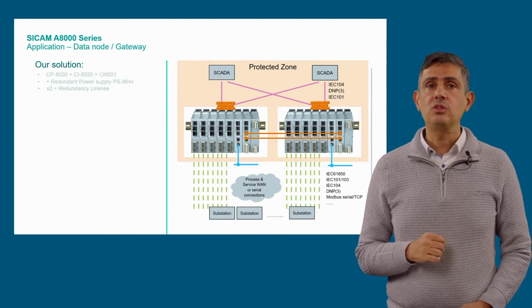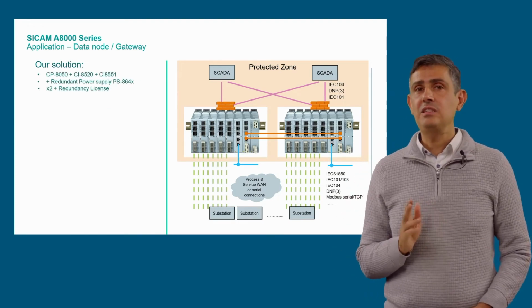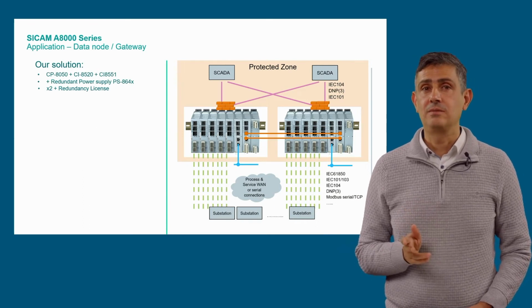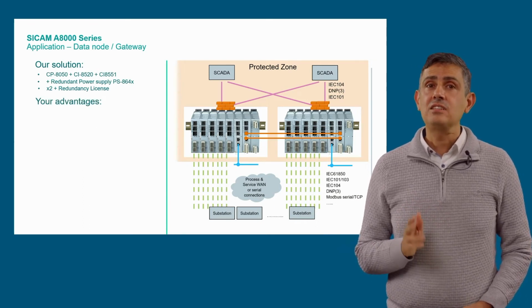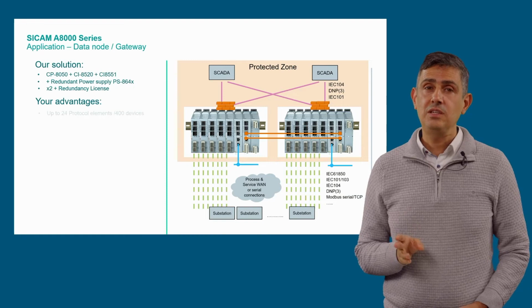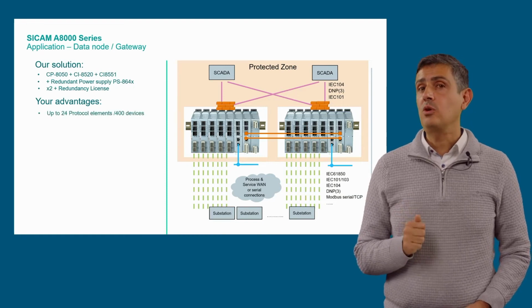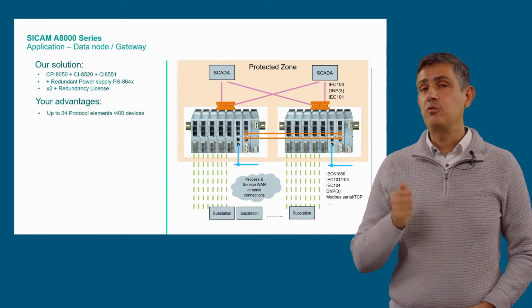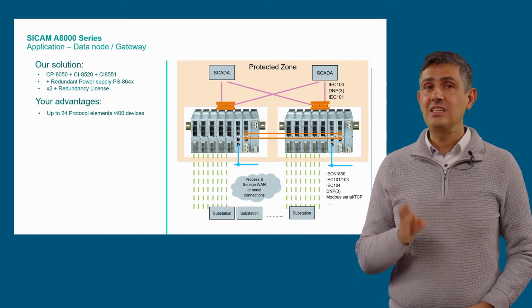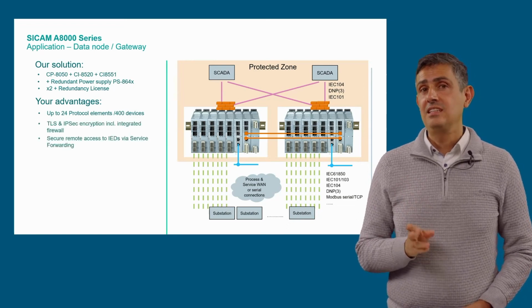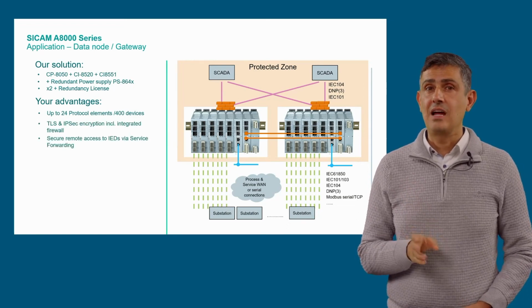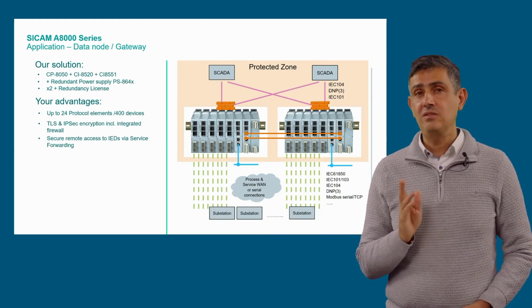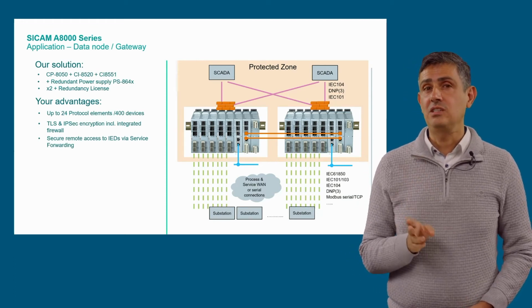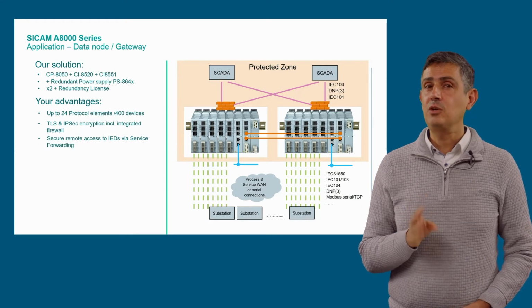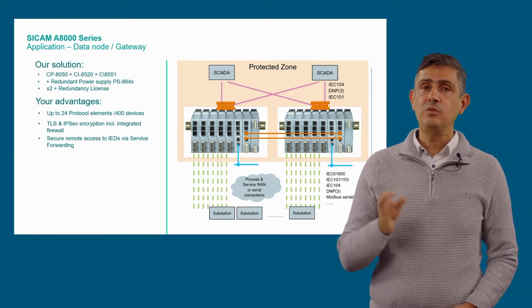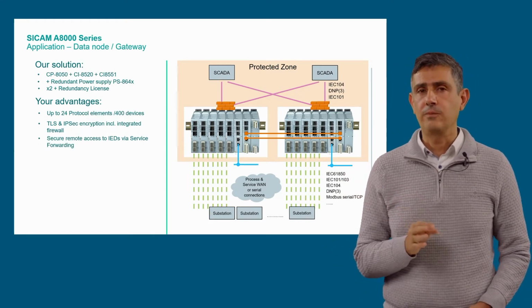Our solution could consider a redundant CP8050 with extension interfaces. The advantages of this implementation with a CP8050: up to 24 protocol instances can be supported and up to 400 stations can be connected to the data node. TLS and IPsec encryption and the integrated firewall in the CP8050 ensure maximum security, while IEDs can be accessed securely from the upper levels through the RTU via service forwarding.